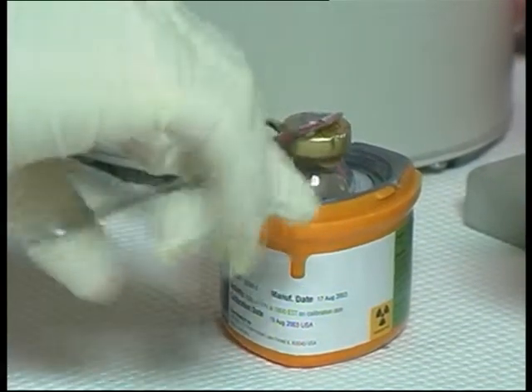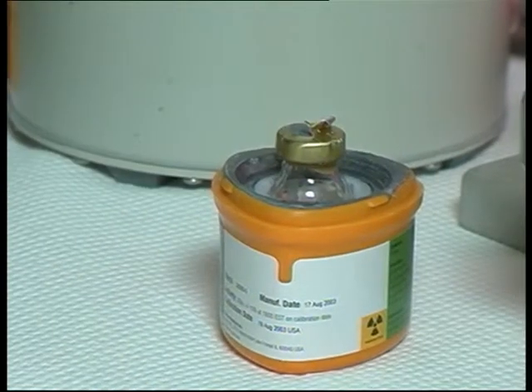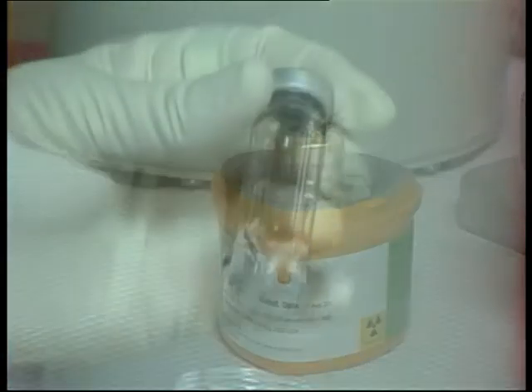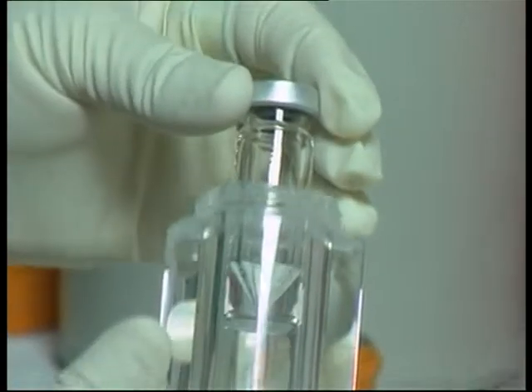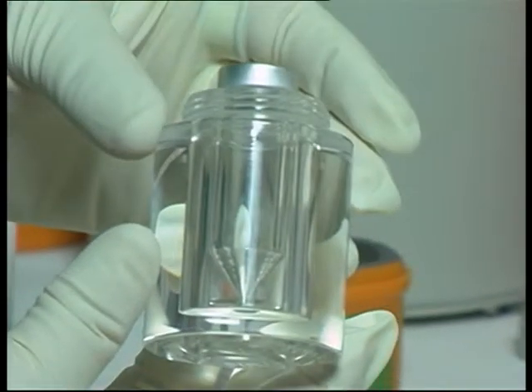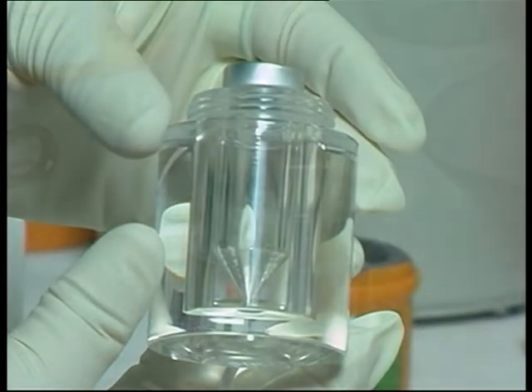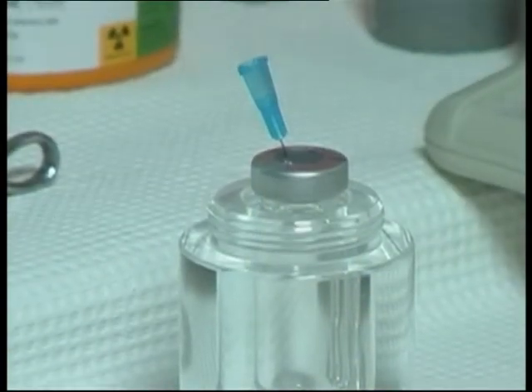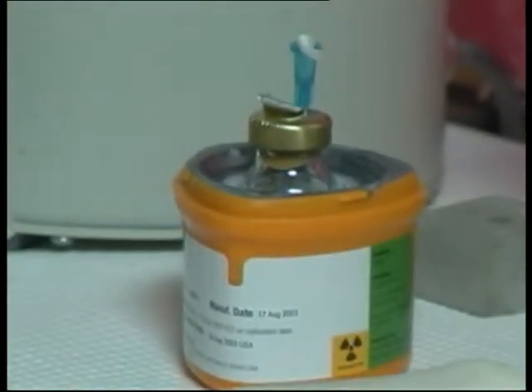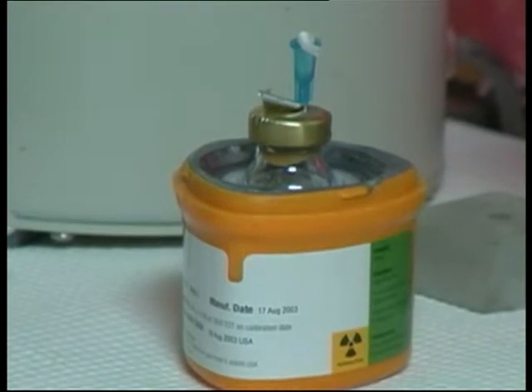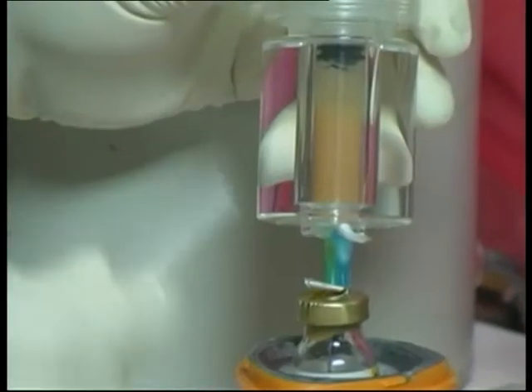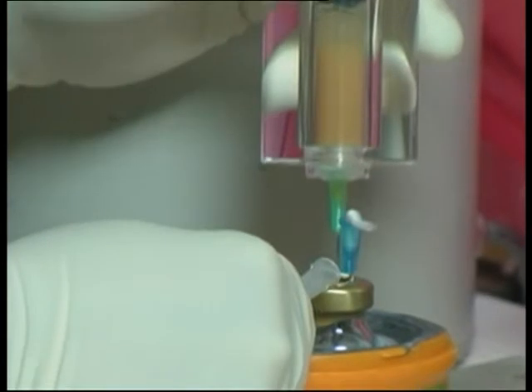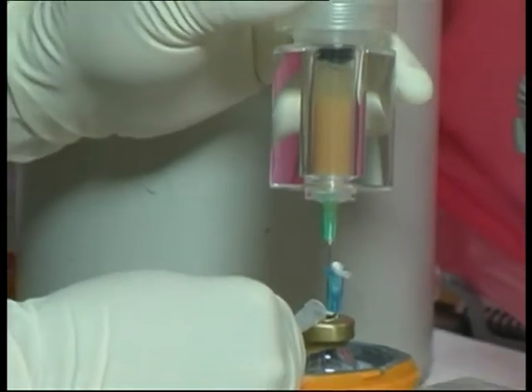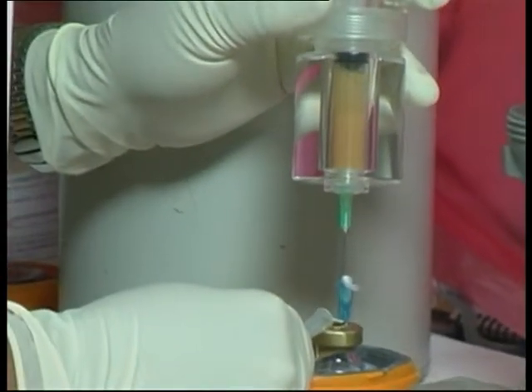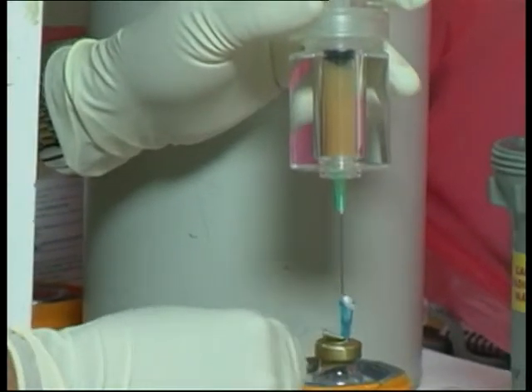To maximize shielding, remove only part of the crimp seal on the shipping vial. The V-vial is to be placed in an acrylic holder before transferring the microspheres. As well, the shipping vial and the V-vial should be close together to minimize transfer distance. Once the dose is drawn into the syringe and the needle is clear of the slurry, a slight pullback on the plunger will reduce the chance of leakage from the tip of the needle.